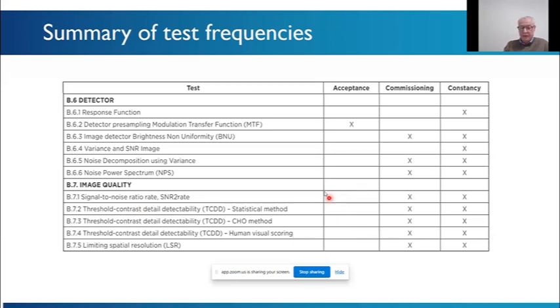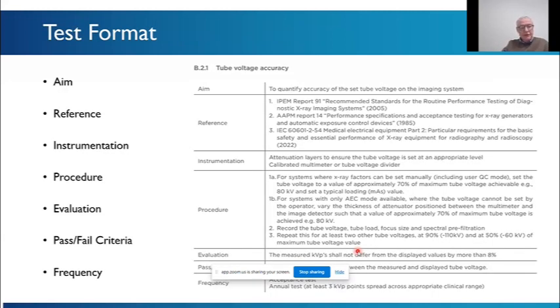The manufacturers won't be doing these kinds of things, but we will be doing commissioning to try and examine the imaging performance of the system, and then followed up by constancy testing. And then the famous limiting spatial resolution as well at the end. That's tested as a detector geometry and also as a system or clinical type of geometry, and I'll explain those in a minute. So each test has got its own format.